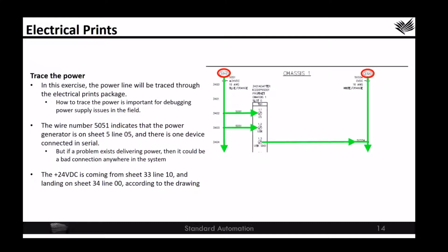If a field device fails, it's usually one of three things. Either the power supply to the device is not working, the ground is not returning the power correctly, or the common's not returning the power correctly, or the signal is not being sent properly. All three of those actions will require you to trace the electrical circuit through the electrical prints package. What we're about to go through is the same steps that you'll need to go through for debugging most electrical issues, either with the power, the signal, or the ground or common line.